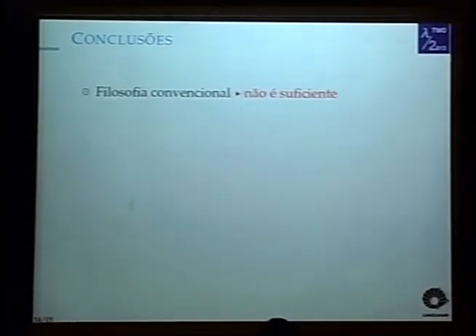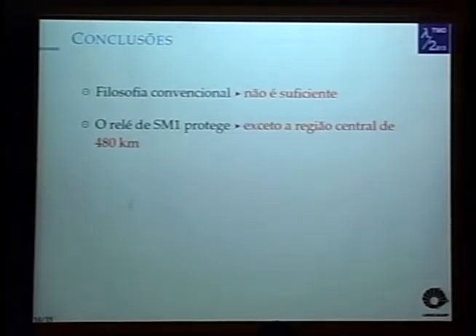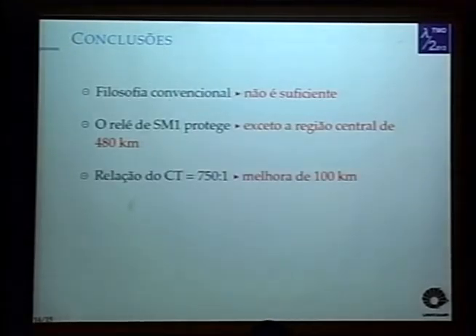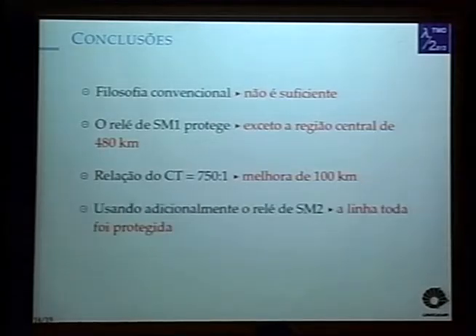It's important to highlight that the conventional protection philosophy for long-distance transmission lines is not enough to protect the AC link during energization tests. The relay located in Serra da Mesa 1 protects the line, except a central region of 480 kilometers. When we change the ratio to 750 to 1, we have an improvement of 100 kilometers. Using the relay in Serra da Mesa 2, the whole line was protected for the energization test without load, or non-load.